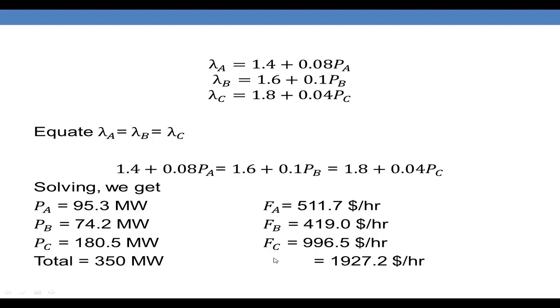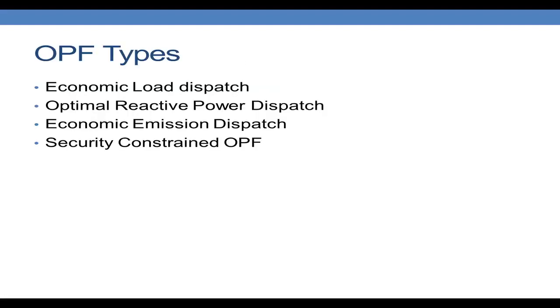We can also implement optimal load flow in ETAP with various constraints. There are different types of optimal power flow. In economic load dispatch we consider only economic factors such as fuel cost and energy price from the grid. In optimal reactive power dispatch we try to minimize reactive power. In economic emission dispatch we consider emission as a constraint to reduce. And in security-constrained dispatch we take various contingencies into consideration.